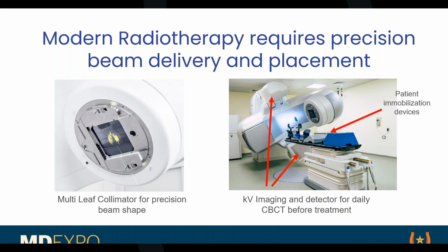Now we have what are called multi-leaf collimators, which you see on the left. The collimation device has these little leaves that you can shape into pretty much any shape you like. And what we do with that is, as the machine rotates around the patient, we change the shape dynamically so that it's continually changing. We're optimizing the beam so that we can deliver the right radiation to the tumor and minimize what's going to the other areas of the patient.